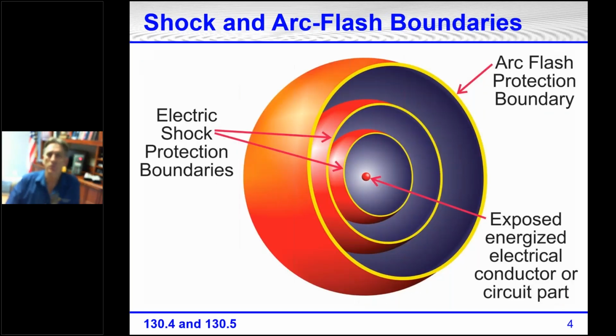All right, so jumping right in, there are two types of boundaries for our electrical safety in the workplace. We have an arc flash boundary, and we have shock boundaries. There's one arc flash boundary. We have two shock boundaries. Several editions back, we had 3 shock boundaries. We used to have a prohibited approach boundary, but that was deleted. So now we have 2 shock boundaries, the restricted approach boundary and the limited approach boundary. We're going to look at that in a few minutes.